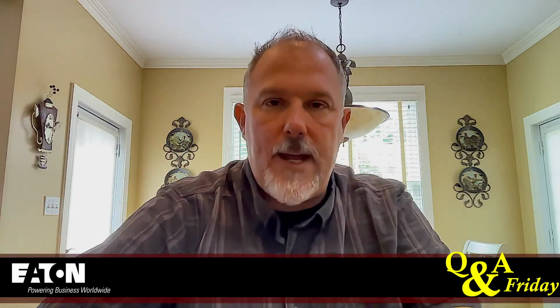and you got to be careful, right? So I have my PE license. Walter, you might have yours too. I picture myself on the stand, and they say, so Mr. Dimitrovich, you added half a millisecond or whatever on your curves outside of what the manufacturer proposed. Yes, I did. And apparently that wasn't enough, because this was not maintained and the incident energy was way higher. It took that breaker a lot longer to open. Where did you get your numbers from? Well, I got those from the book of Thomas Dimitrovich. It wasn't enough, was it? No. Do you really know what you're doing, Tom?